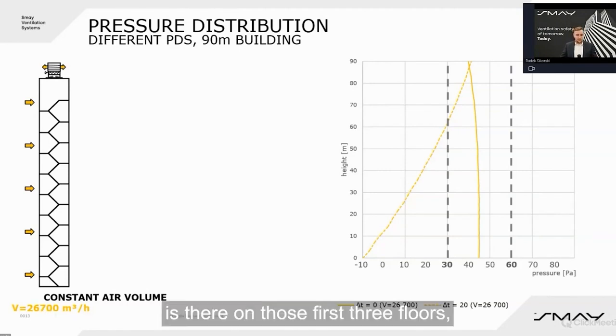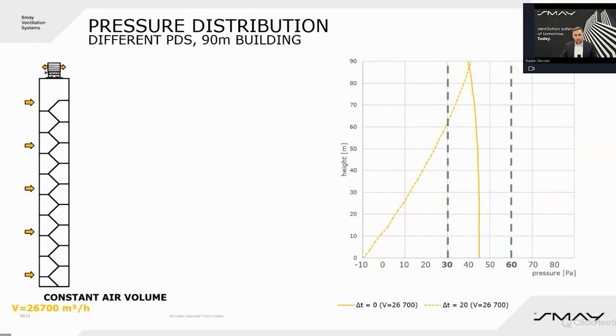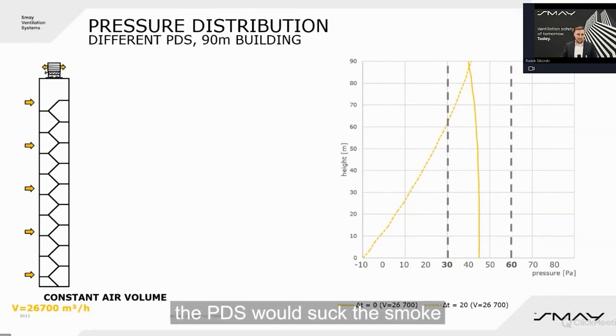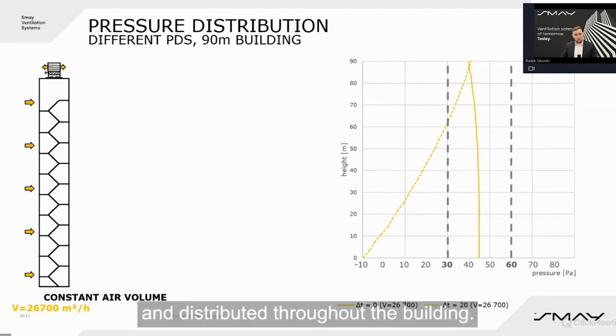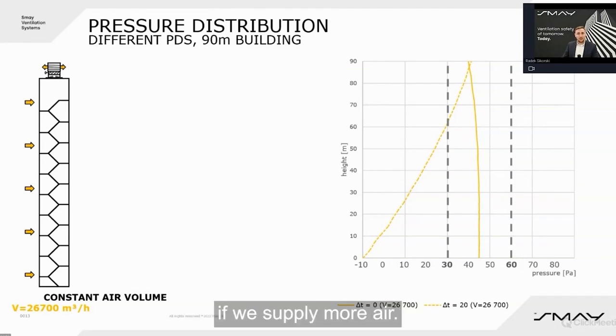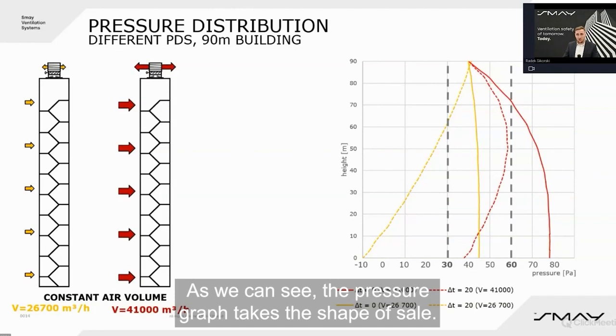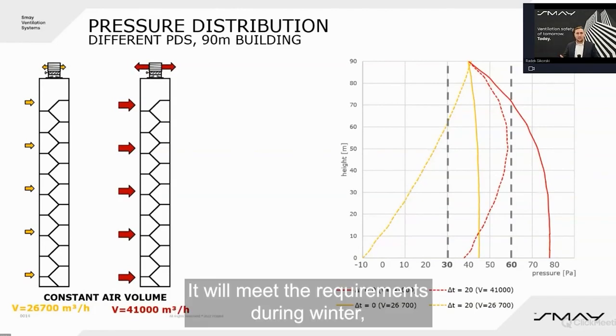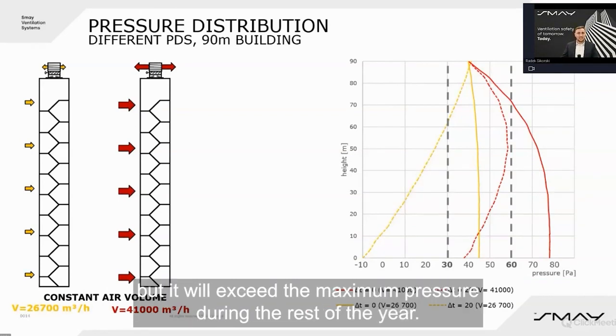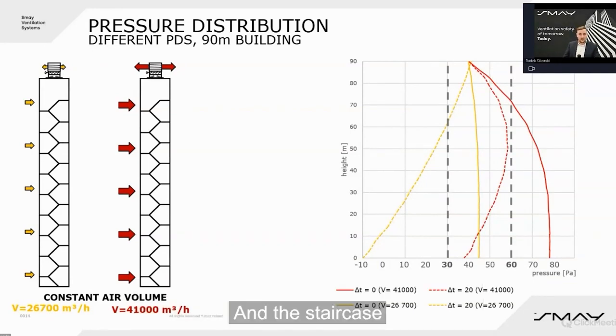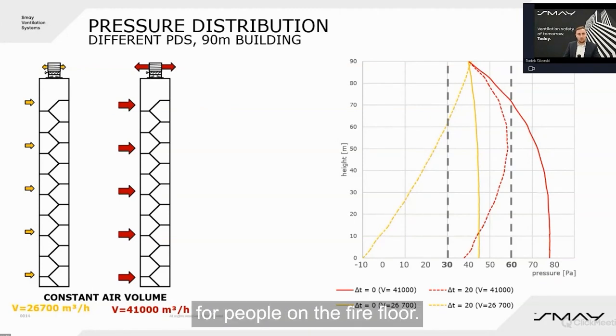But during winter, shown as a dashed line, we have underpressure on the first three floors. If a fire occurs on those first three floors, the PDS would suck in smoke and distribute it throughout the building. If we supply more air, the pressure graph takes the shape of a sail — it will meet requirements in winter, but will exceed the maximum pressure during the rest of the year, making the staircase a trap for people on the fire floor.